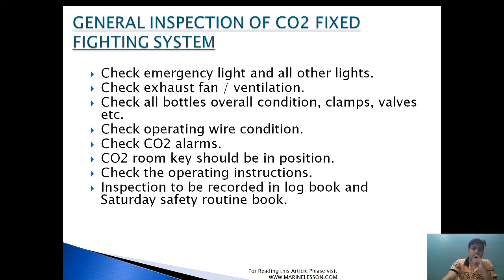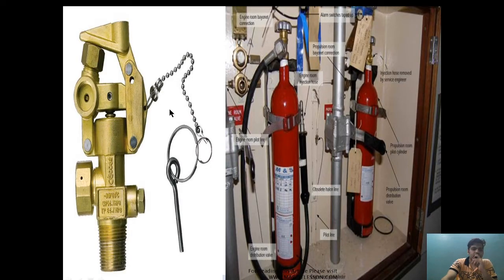Check the CO2 alarm — open the cabinet door and confirm the alarm activates. The CO2 room key should be in position. Check the operating instructions. Inspection should be recorded in the log book and the Safety Training Book. Also check the lock pin — when the CO2 system is not in operation or being transported, this lock pin is placed to prevent accidental puncturing. Each pilot bottle has the capability to puncture the bulk CO2 system.